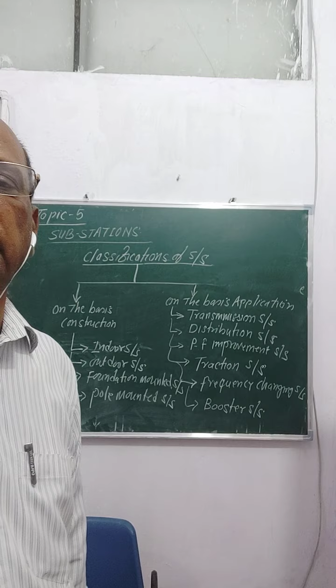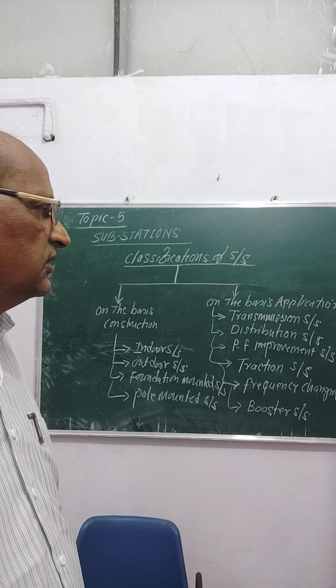Then power factor improvement substation. These substations are generally installed in areas where power factor is very poor. There are two types of power factor improvement substation. One is used up to 33 kV, with static capacitors to compensate the power factor with the help of kVAR compensation. The second is on 220 kV or 400 kV, when a large area is to be covered and the inductive load is very large. They use synchronous motors operating at leading power factor with over excitation. The over excited synchronous motor running at leading power factor is part of the extra high voltage power factor improvement substation. That improves the power factor by feeding negative kVAR into the system.